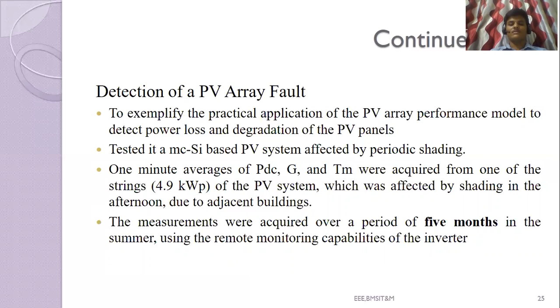The measurements were acquired over a period of 5 months in the summer using the remote monitoring capabilities of the inverter. As we see in this graph, which is PDC over the ratio of PMP naught versus time, with the relative power estimation error percentage. The prediction accuracy of the resulting model was under 5% relative error under nominal operation conditions with no shading. This can be observed in the figure in red color, showing the measured and model predicted array power for a clear sky day. In the afternoon, the PV array is shaded, causing power loss, which can be detected by large power estimation error.